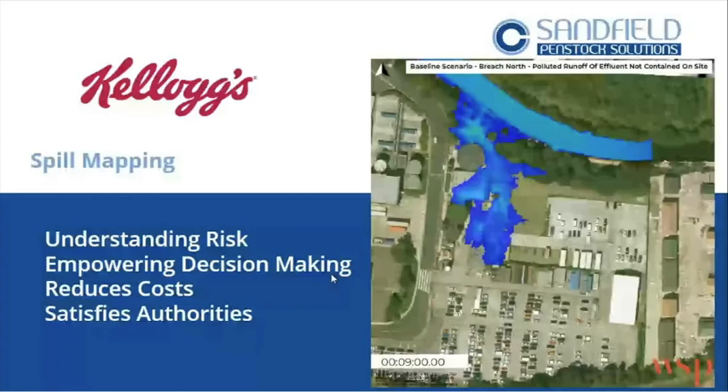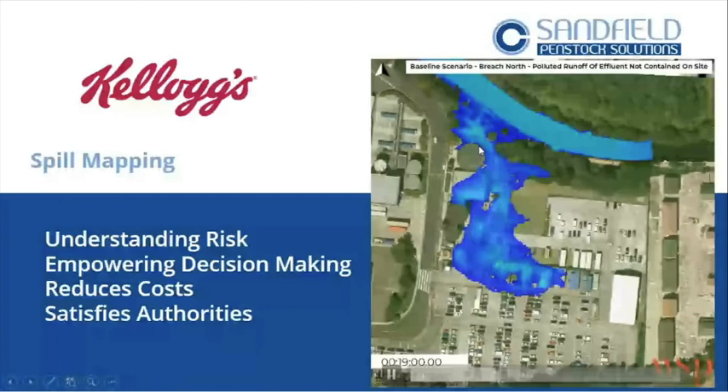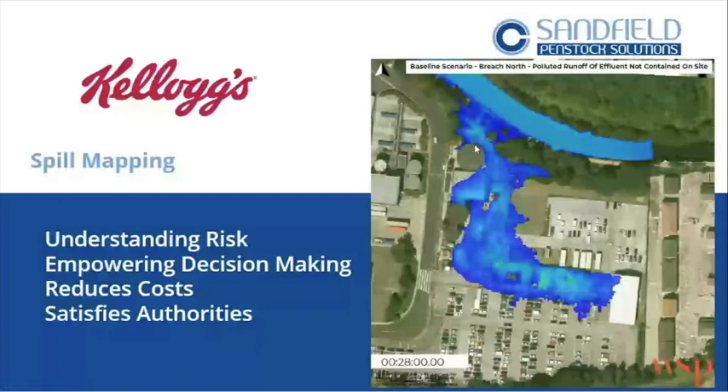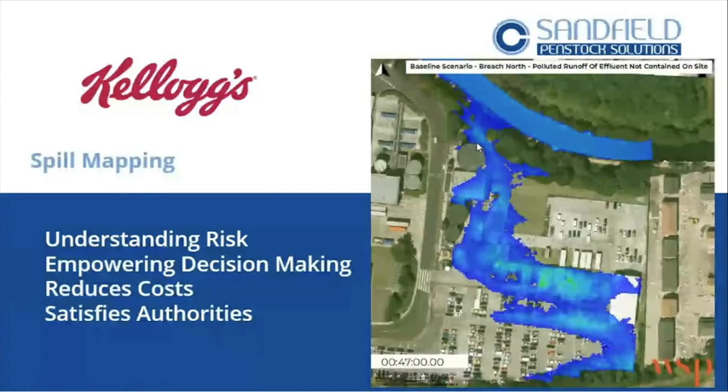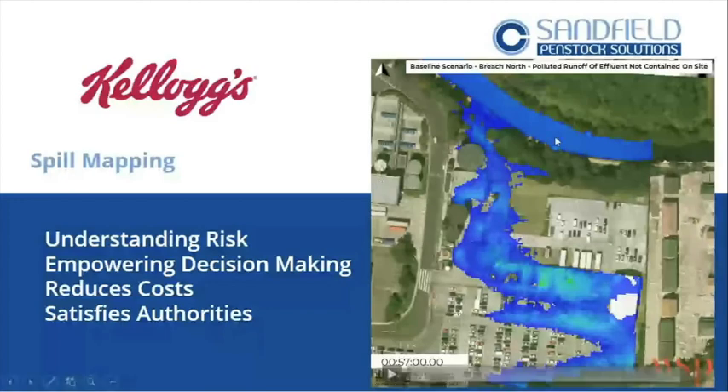This is the model. What you've got here is where we identified a hole in the balance tank — that hole would leak out at 450. What you see from topography and drainage analysis is, with the drainage isolated, this is the above-ground flow path — this is how that liquid would shoot out of this site if no protection was done. At that moment this was their problem — to evidence to the business that they needed to do something because the water was spreading everywhere, uncontrolled, with various breaches and the main pollution risk into the adjacent canal.